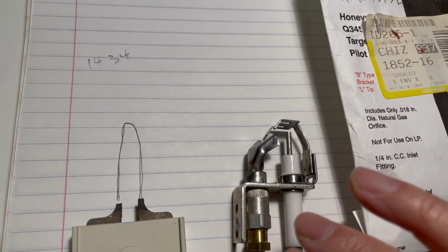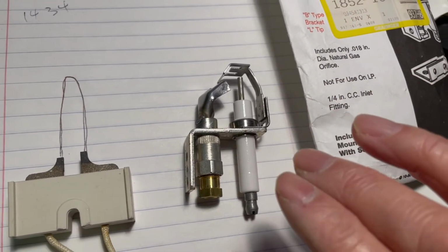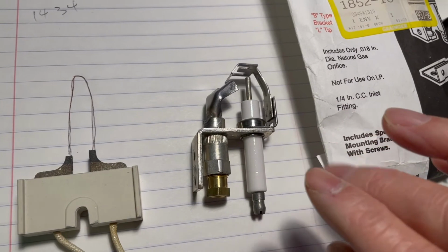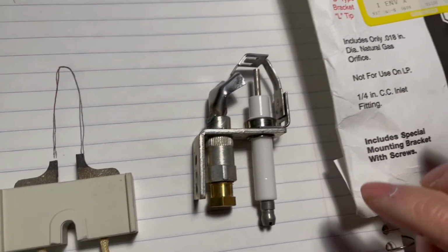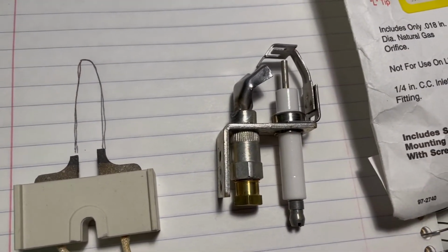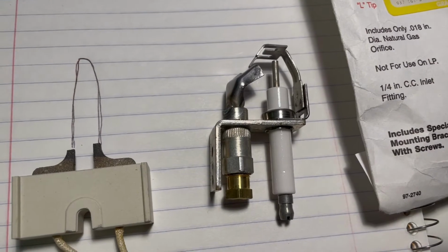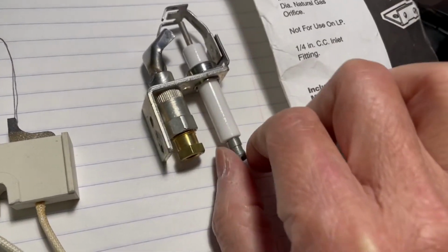So by how many flashes, you would know what the error code is, and then you can see what the problem is. And for my boiler, I actually get a digital display, so I don't have to guess. I look at it. If it's at low flame current, then I know that there's a problem with the igniter. Maybe the cable, there's a problem.